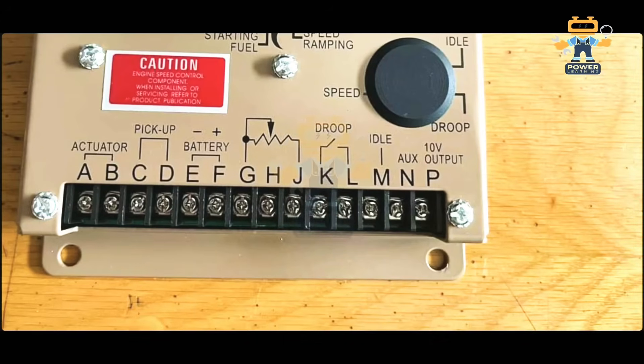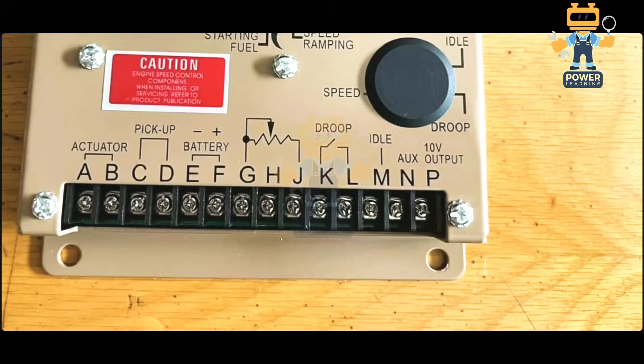After that we have N and P. When we are using synchronizing and we have external speed control, you will connect your speed control wires on terminal number N and terminal number P. So in this way you can connect your two wires for load sharing and synchronizing.